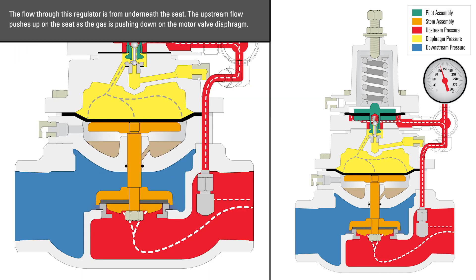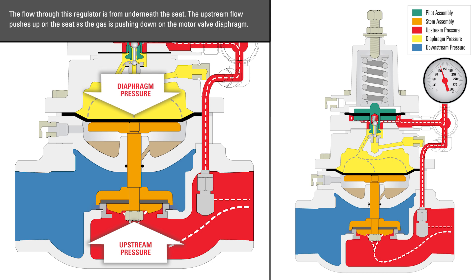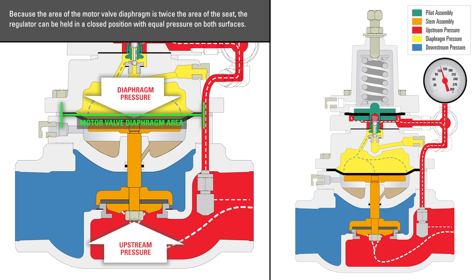The flow through this regulator is from underneath the seat. The upstream flow pushes up on the seat as the gas is pushing down on the motor valve diaphragm. Because the area of the motor valve diaphragm is twice the area of the seat, the regulator can be held in a closed position with equal pressure on both surfaces.